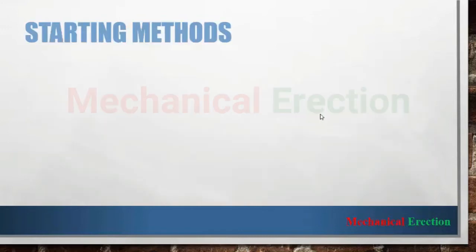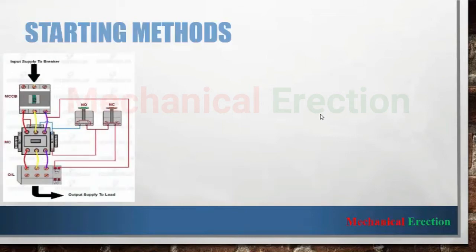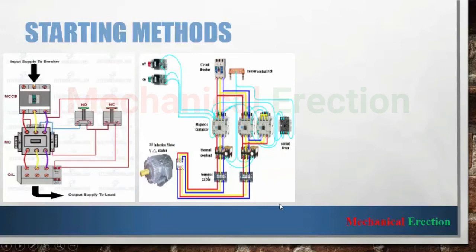Now I am discussing the starting methods of electric motors. There are different starting methods, but I will discuss a few here. First is direct online, which is the most common in the practical field to start motors. This is for either star or delta connection at the motor terminal, where the motor is connected through the incoming circuit breaker, then the magnetic contactor, then the overload relay or push button which indicates the start and stop status of your motor.